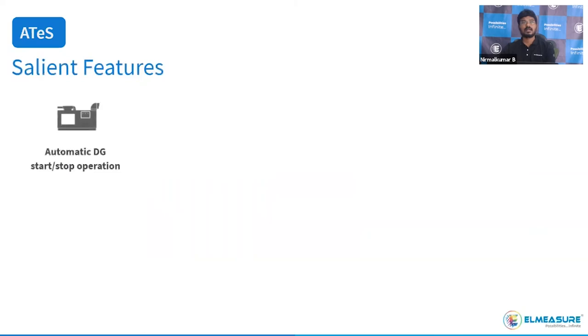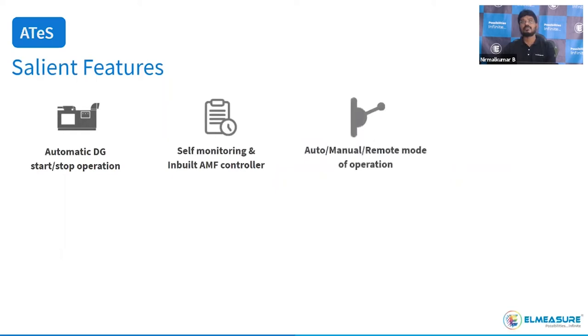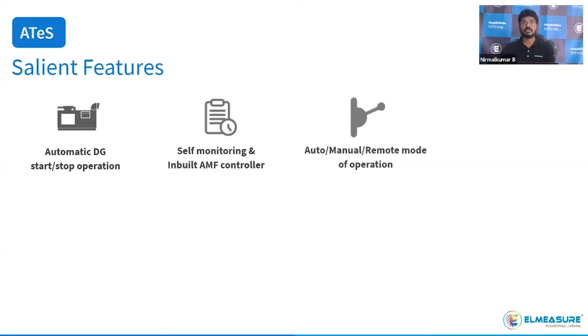Salient features: our ATS has the facility to start the backup generator during mains failure, plus self-monitoring and an inbuilt controller. Unlike competitors' remotely operated ATS that require an external AMF or PLC command, Elmeasure provides three modes of operation. Auto mode is the primary operation. Manual mode allows changeover via manual handle without any power interruption if a control-side issue occurs.